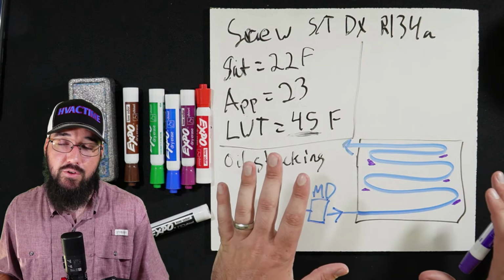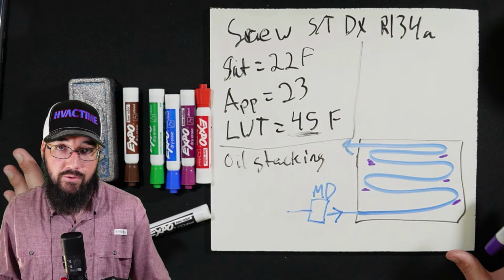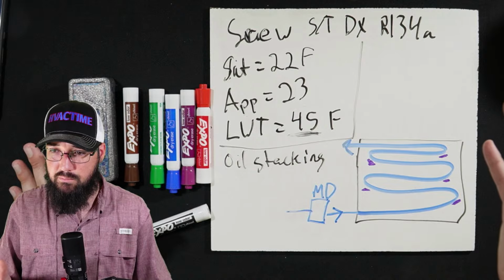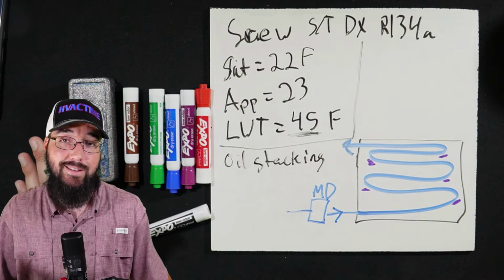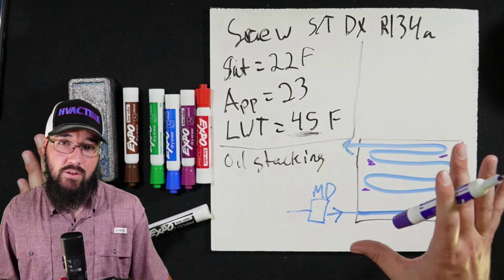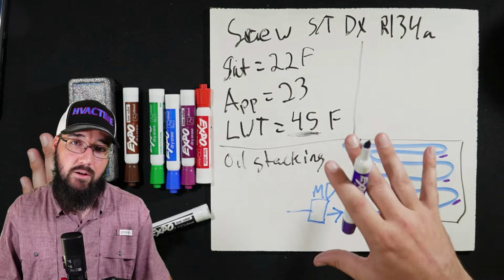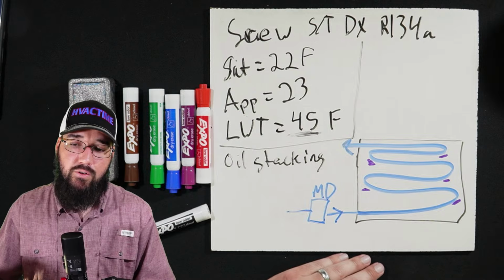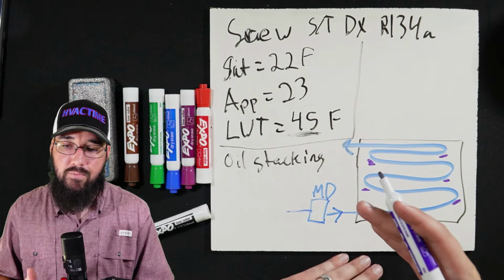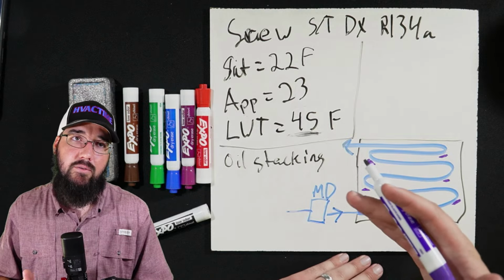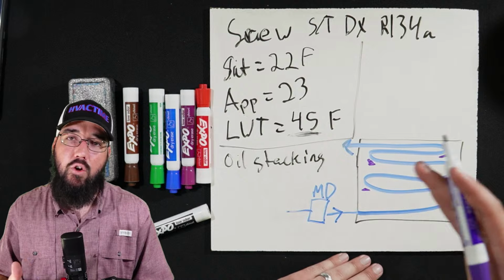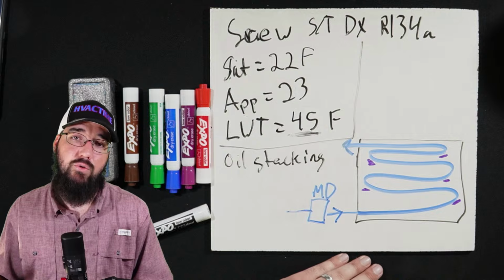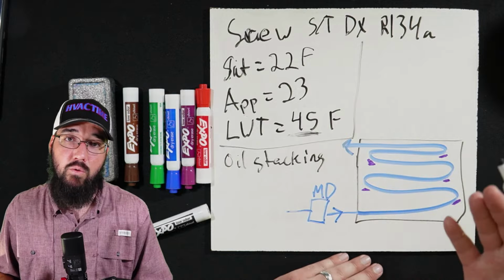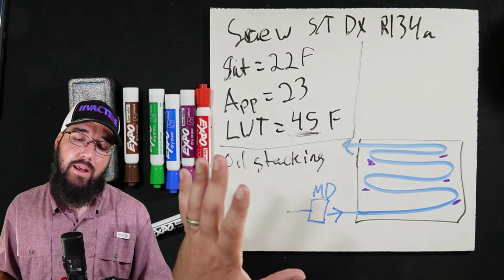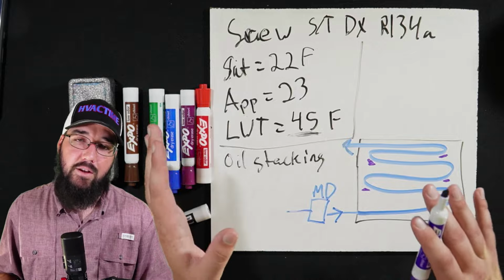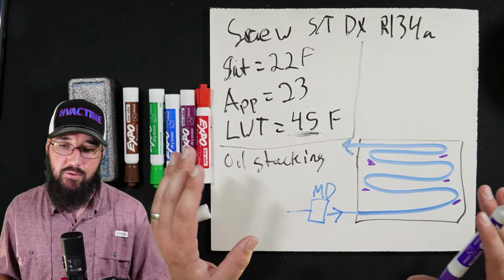And so if this machine is running at minimal load alongside several others simultaneously, I think you said there's five other chillers potentially online. I'm assuming you mean five others online at the same time. When you start to get into those conditions, and this is something that doesn't get managed at the chiller, it gets managed at the automation level, the other plant controls, when you start to have the load decrease across all those chillers, it is best to unload some of those so that the other ones can get more load on them, because there is a breakover point where it's detrimental to run too low of a load for an extended period of time on these machines.